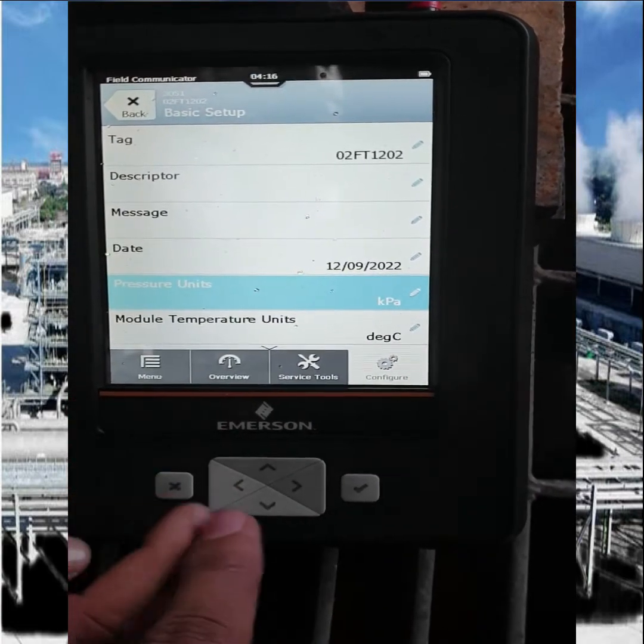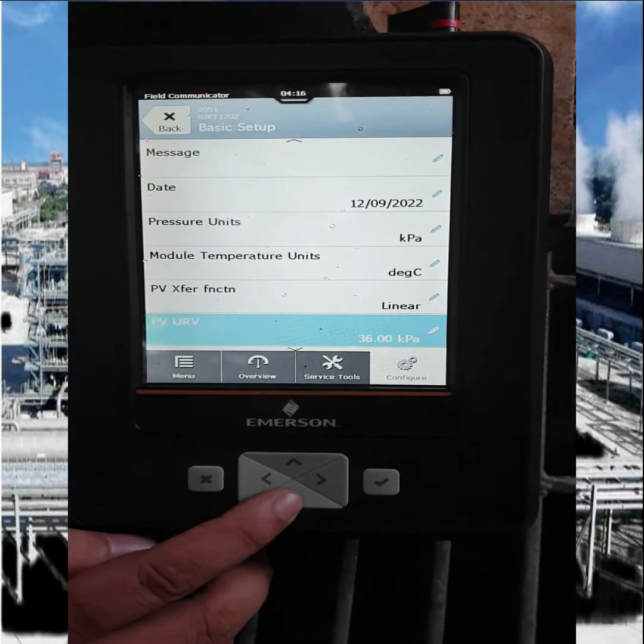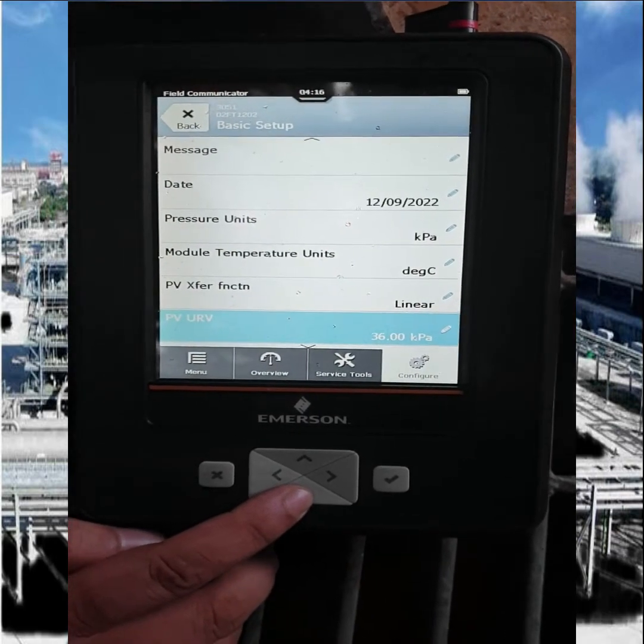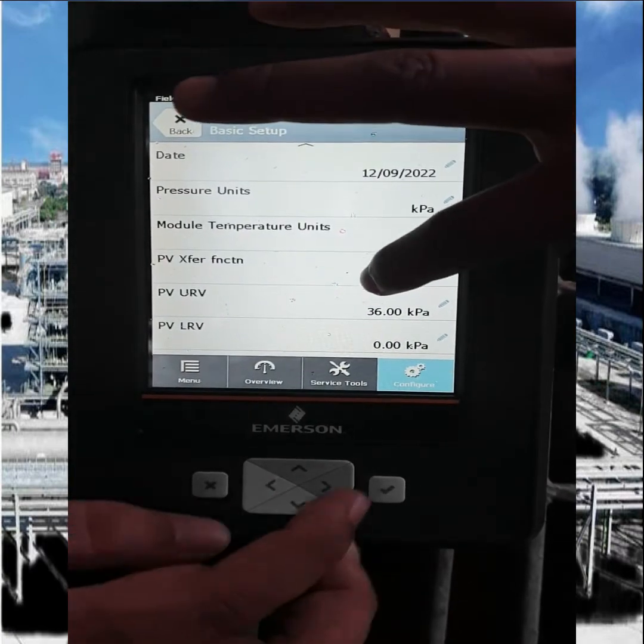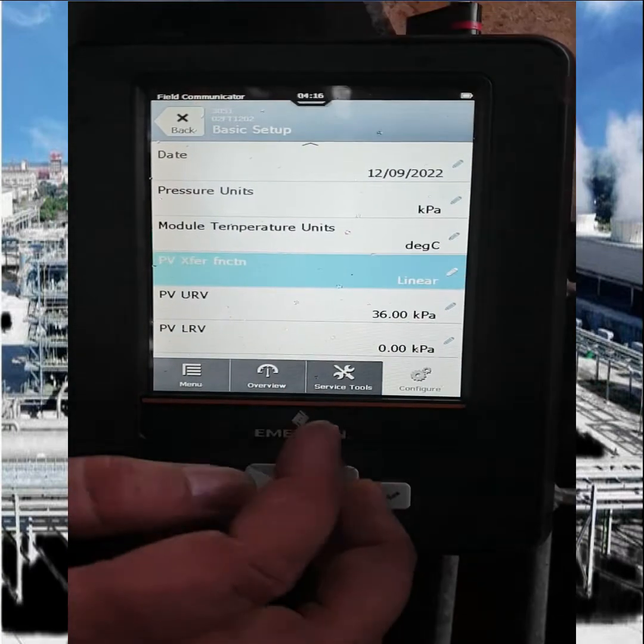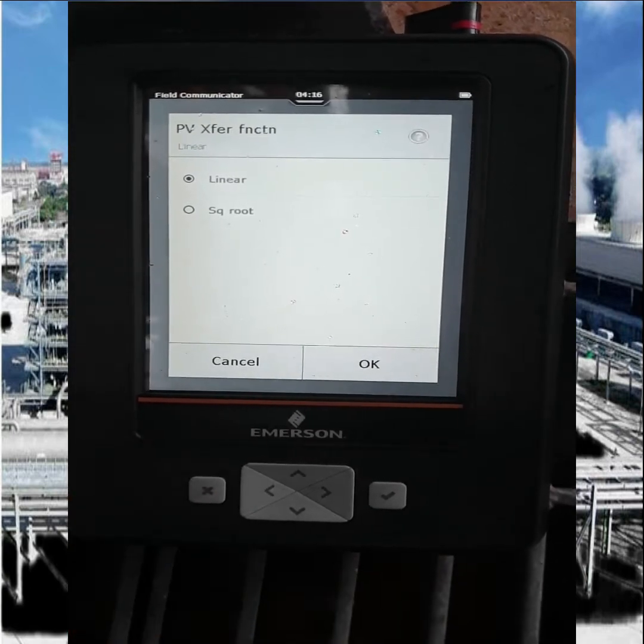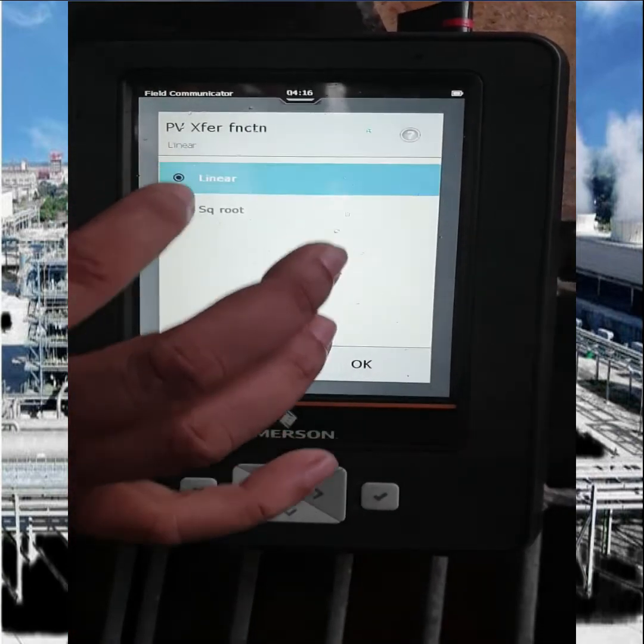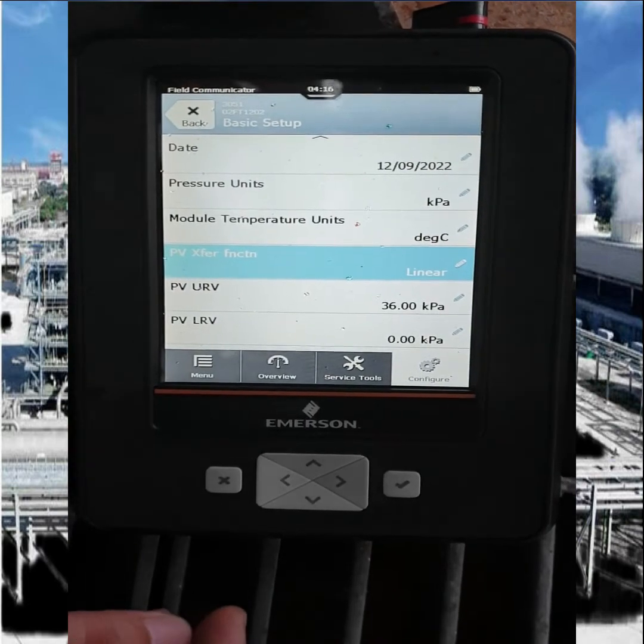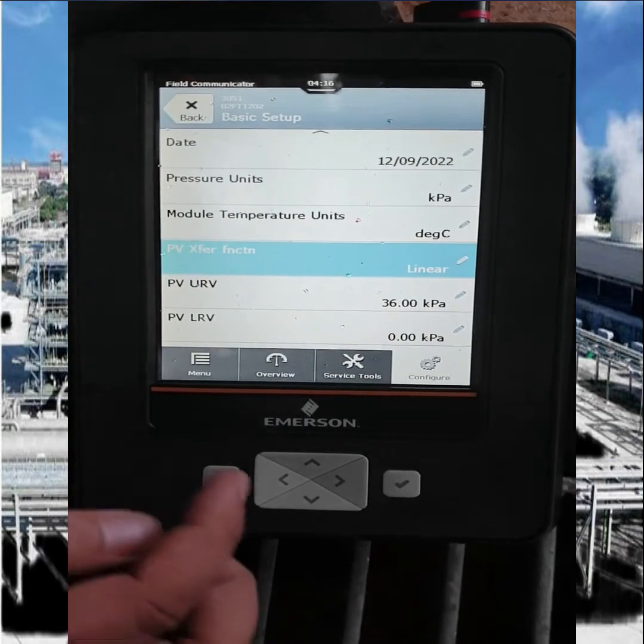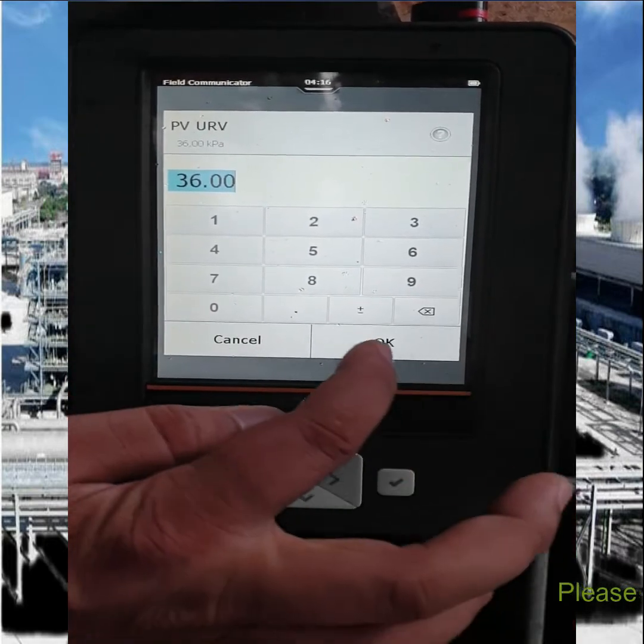Here the transmitter needs to be configured for the PVX function — that means selecting whether our transmitter is linear or square root. Go to the transmitter function and select accordingly. Our transmitter is linear, so we select linear and press OK. If your transmitter is square root, select square root and press OK.